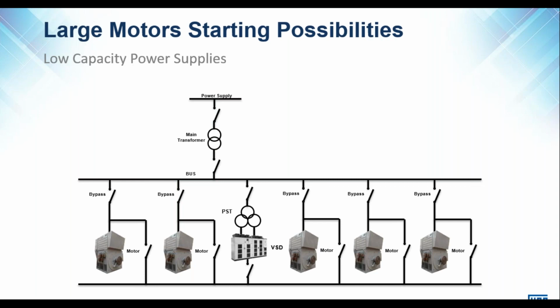Another application where this is useful is if you want the advantage of starting motors and loads with a VSD, but to reduce the capex, you can install one VSD and start multiple motors. This is useful, for example, in pump or fan applications where you do not necessarily need to vary the speed of all the pumps or all the fans. So you can still start those fans or pumps with the VSD, bypass each one of them once they are started, and then keep one in circuit, for example, to adjust your flow rate on PID control.